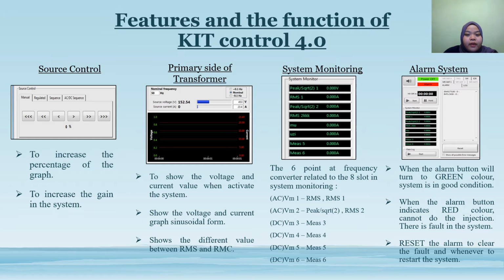Only VM1 and VM2 will use the AC source, and other points will use DC source. VM1 point at the frequency converter contacts with 2 slots, which are RMS and RMS1. VM2 also contacts with 2 slots, which are peak over square root 2 and RMS2. For VM3, VM4, VM5 and VM6, they only contact with 1 slot each, which is measure 3, measure 4, measure 5 and measure 6. And the last feature is the alarm system.